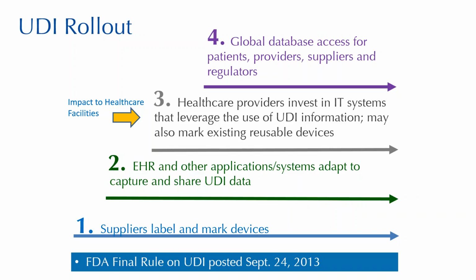So the first set of compliance dates affected class three devices. Class one devices, which include the majority of reusable surgical instruments, will need to be marked by September of 2020. By that date, new surgical instruments must bear a UDI as a permanent mark on the device itself if that device is intended to be used more than once or reprocessed before each use.